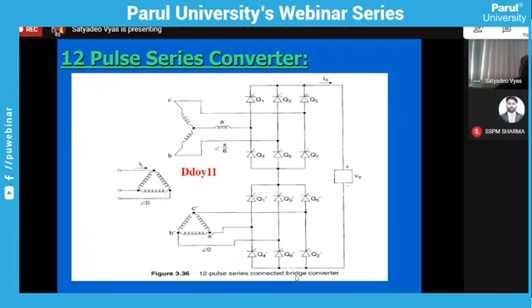Current in the star winding, you can see, is minus 1 by 5 cos 5 omega t. This is the 5th order. Plus 1 by 7 cos 7 omega t. Current in delta is plus 1 by 5 minus 1 by 7. If you add the net current, the summation of star winding and delta winding, the 5th order and 7th order harmonics will get nullified. So the lowest order harmonics present in the 12 pulse configuration will be 11 and 13.